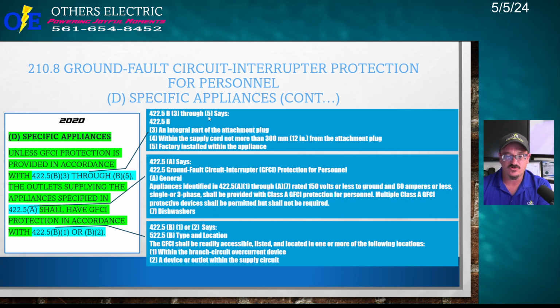422.5B, 3 through 5 says an integral part of the attachment plug. 4 says within the supply cord, not more than 12 inches from the attachment plug, or factory installed within the appliance, okay? So unless these pieces of equipment, appliances that we're going to specify next, have those things in them, the circuit needs to be GFCI protected. Okay, ready? The outlet supplying the appliances in 422.5A.